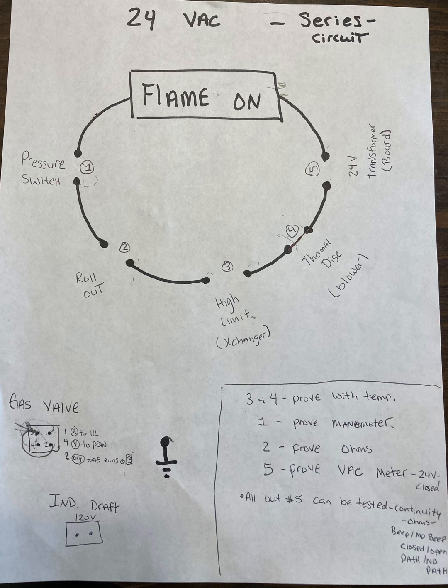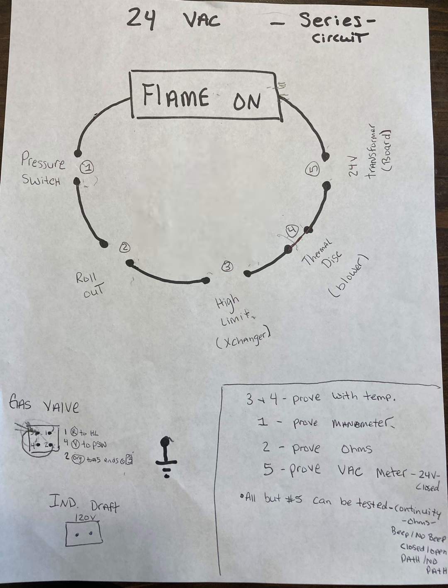Our first switch on my list is the pressure switch, and you really need a manometer to test this pressure switch to see if it's lying or not. If you prove through your hopscotching method that you have 24 volts going into the pressure switch, but you don't have it leaving it, we have an open switch. The highway's open. There is no path, right? Beep or no beep. Beep meaning there is a road there. That switch is indeed closed. The circuit is a closed circuit. No beep meaning there is no continuity. There is no path. There is no circuit. You shall not pass.